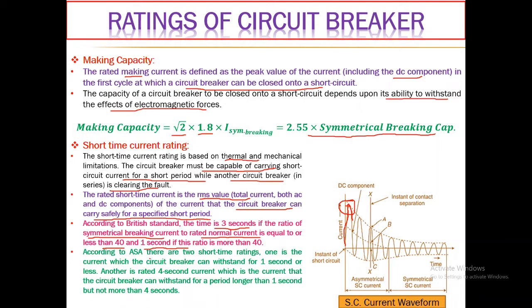According to American Standard there are two specific time ratings: one is the current the circuit breaker can withstand for one second or less, and another is the rated four-second current — the current the circuit breaker can withstand for a period longer than one second but not more than four seconds. The British Standard suggests three seconds; the American Standard suggests one to four seconds.